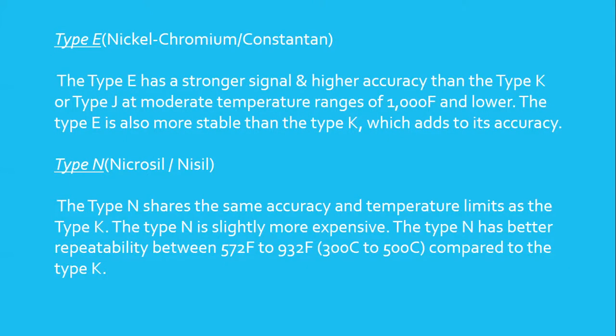Type E. The Type E has a stronger signal and higher accuracy than the Type K or the Type J at moderate temperature ranges of 1000 Fahrenheit and lower. The Type E is also more stable than the Type K, which adds to its accuracy. Type N. The Type N shares the same accuracy and temperature limits as the Type K. The Type N is slightly more expensive. The Type N has better repeatability between 572 Fahrenheit and 932 Fahrenheit, 300 degrees Celsius to 500 degrees Celsius, compared to the Type K.